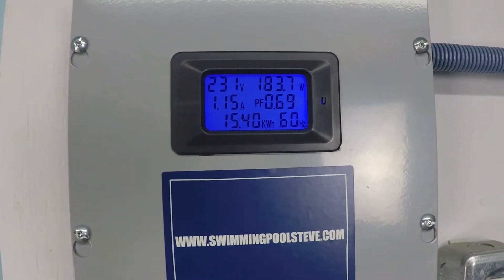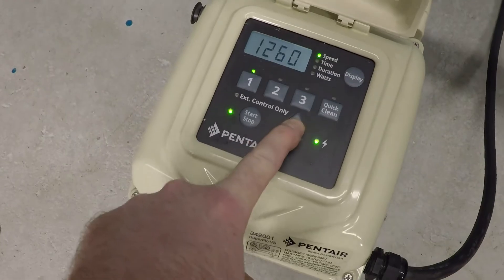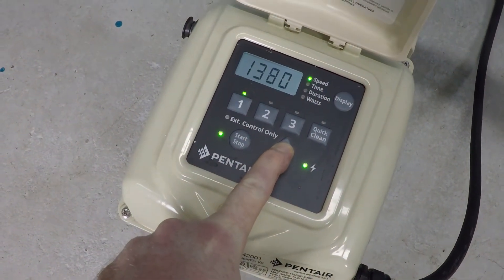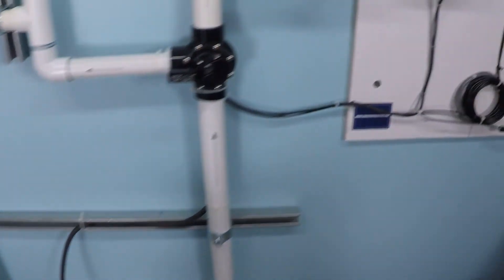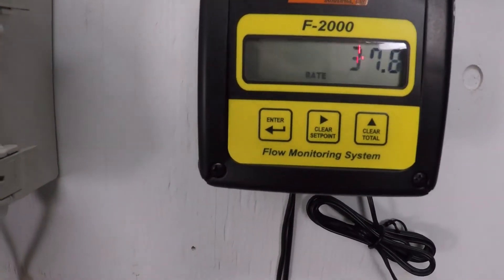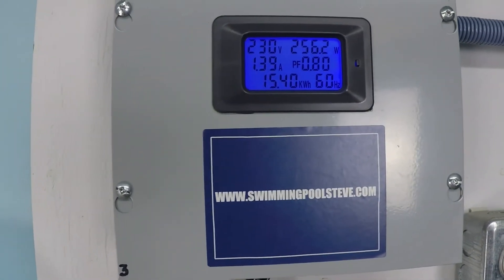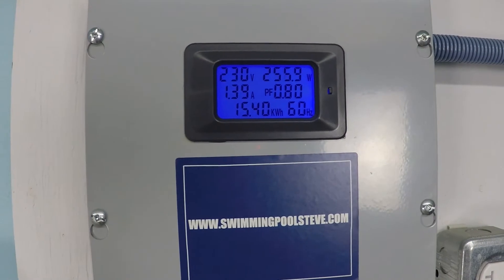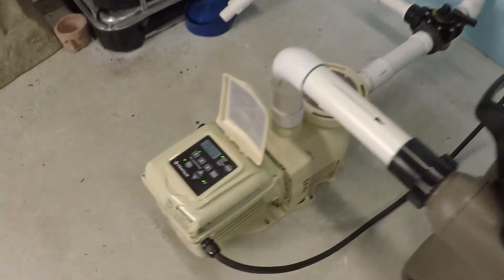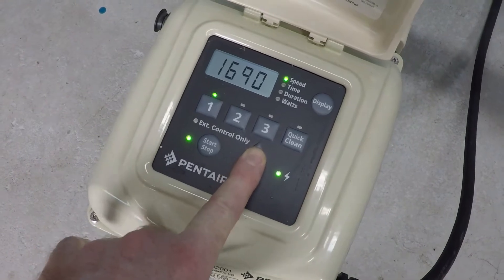At the next speed increment, we're seeing 184 watts and 1.15 amps of current draw. Flow is at 37.5 gallons per minute, with power consumption measuring 256 watts.